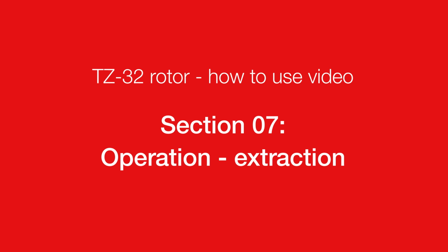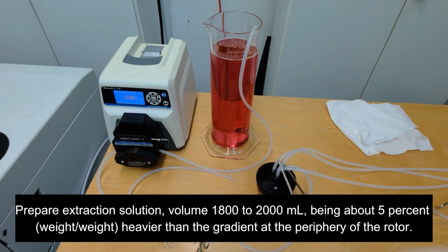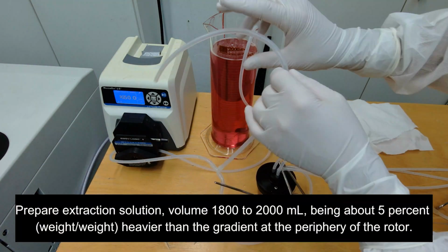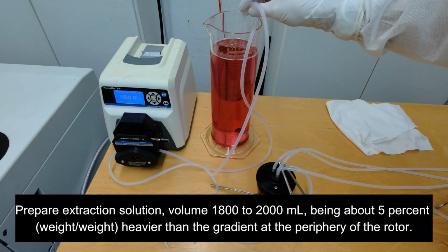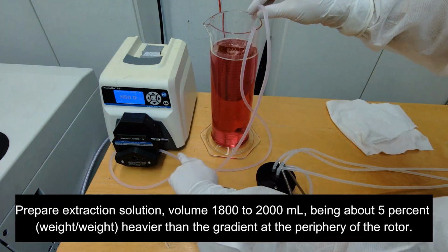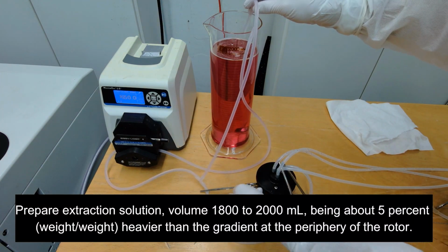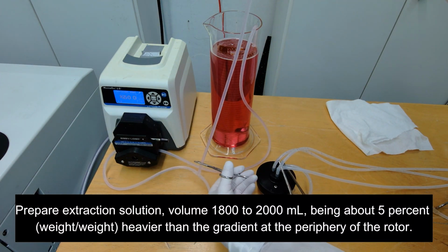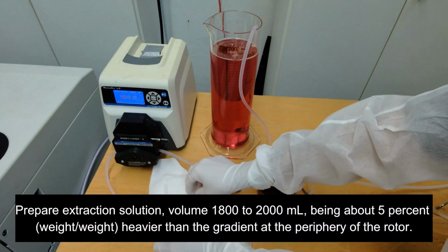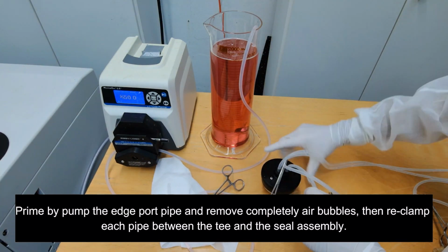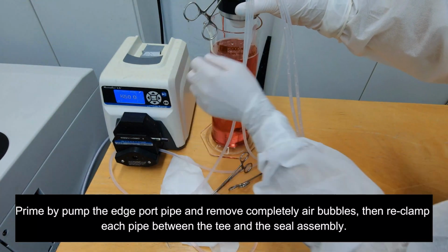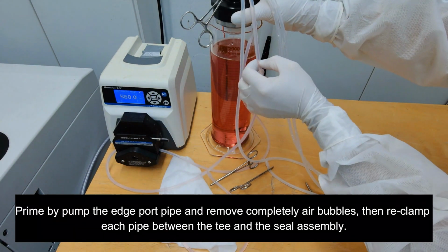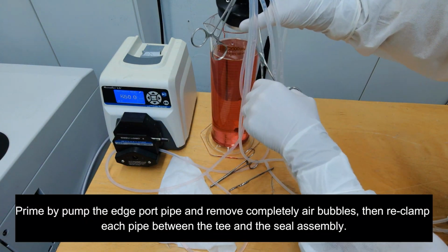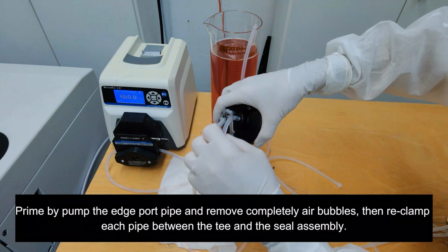How to use video. Section 7. Operation. Extraction. Prepare extraction solution, volume 1800 to 2000 milliliters, being about 5% weight by weight heavier than the gradient at the periphery of the rotor. Prime by pump the edge port pipe and remove completely air bubbles. Then reclamp each pipe between the T and the seal assembly.